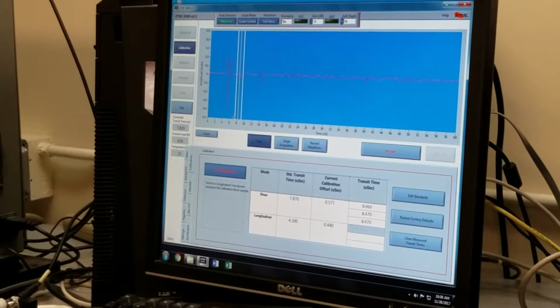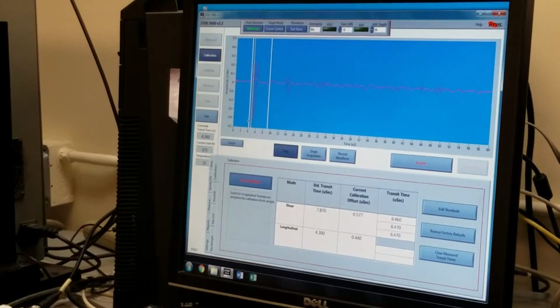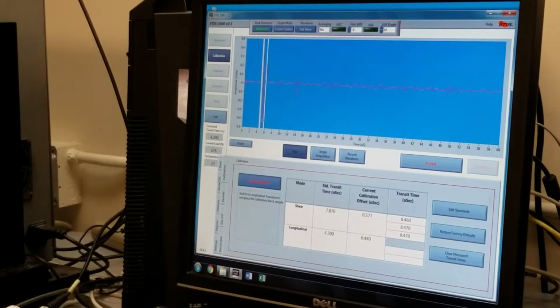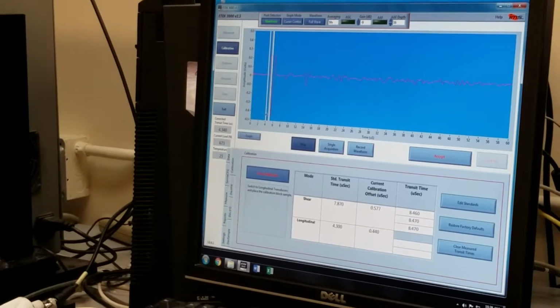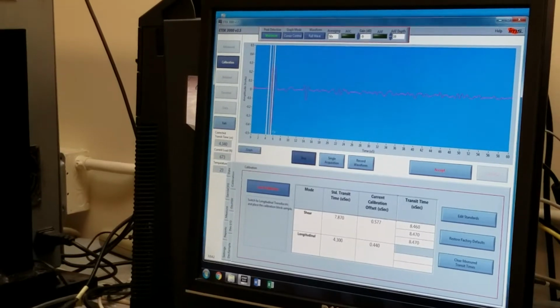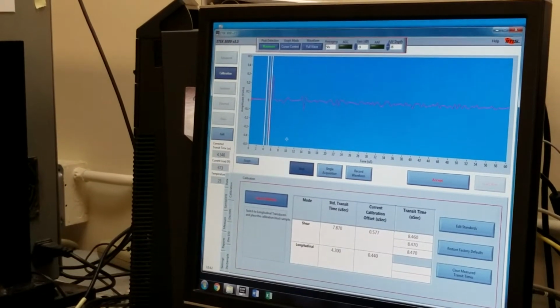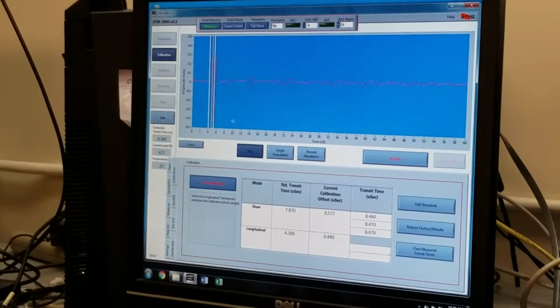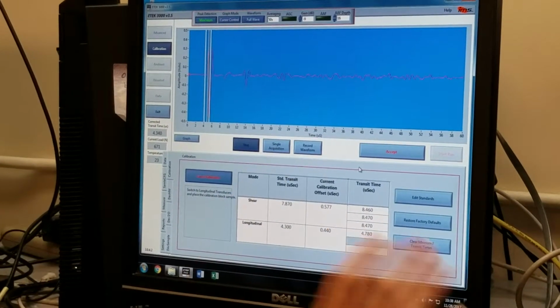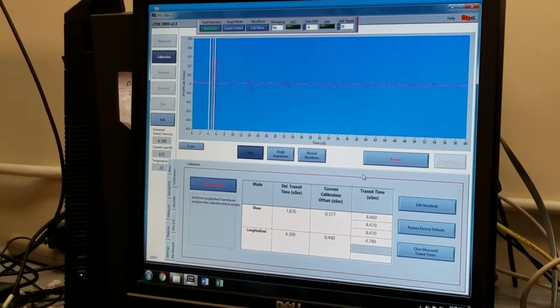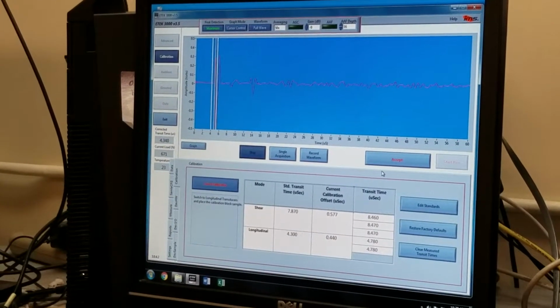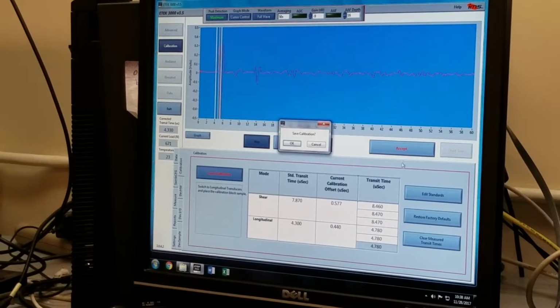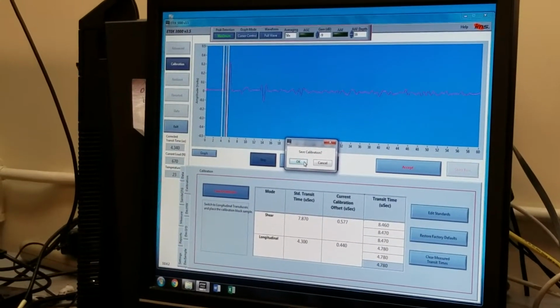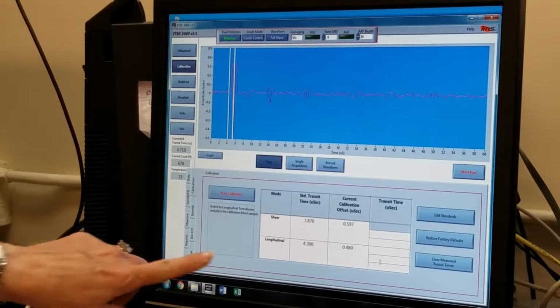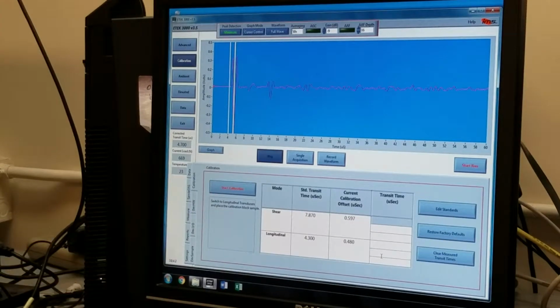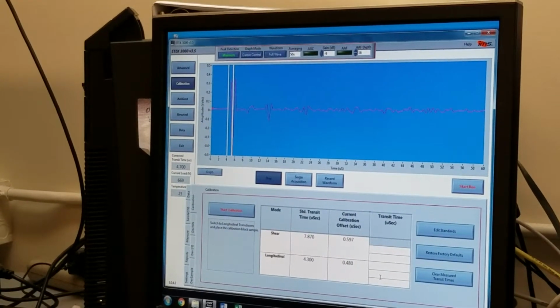Now we're looking at a compressional waveform. I need to change the position that I'm measuring. I want to measure the first peak. So with my cursor control, I'm moving my white windowing so that my yellow vertical line is over the first peak. When I'm ready, I click accept, move the calibration block, click accept again, move it, and click accept for a third time. And click OK on save calibration. At this point, a new offset value has been calculated and we're ready to start a measurement.